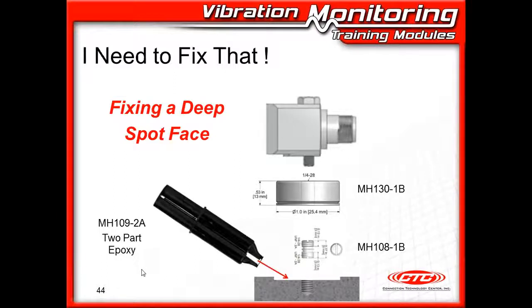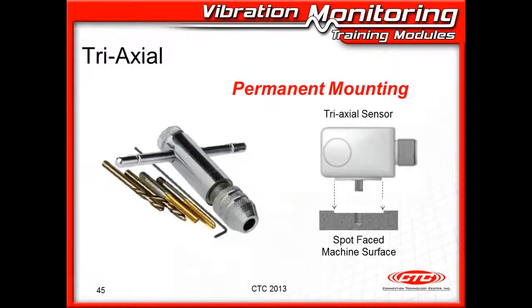And if you need to fix it, well, this is a good time to buy yourself a double-sided mounting stud. Put that mounting stud right into your spot face. Buy a mounting pad that has a through hole. Thread the mounting pad down onto the spot face, and put some epoxy under that mounting pad. Turn it right down into the epoxy, and then bring your side exit sensor down on top of the mounting pad. And that'll fix the problem that you've gone too deep here. You'll get that epoxy in there making good contact, and you'll transmit right up through the mounting pad into the sensor. So that's a real nice fix if you've gotten that spot face too deep.